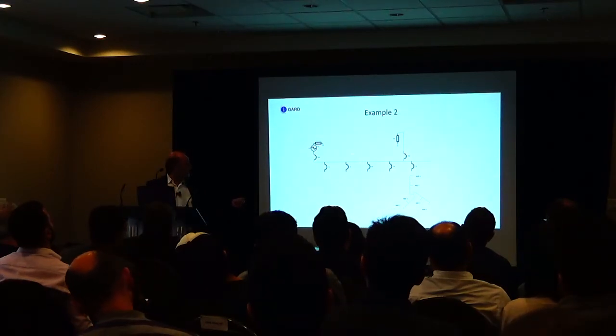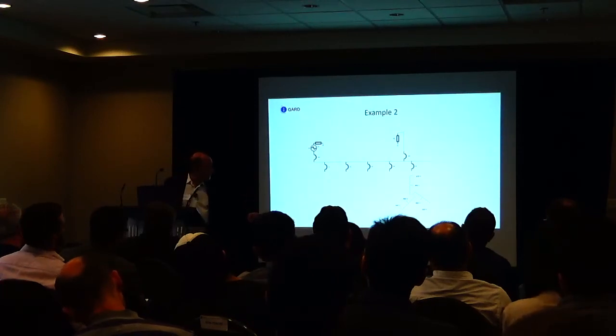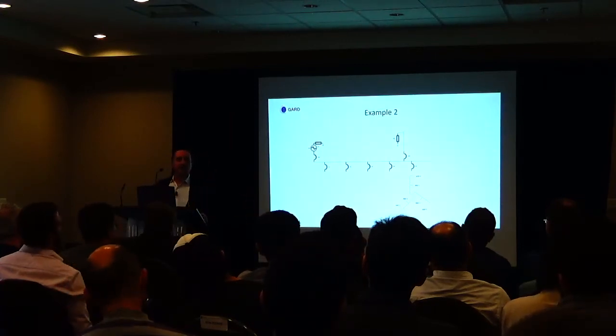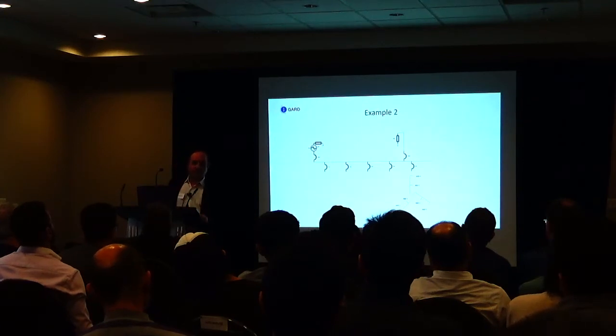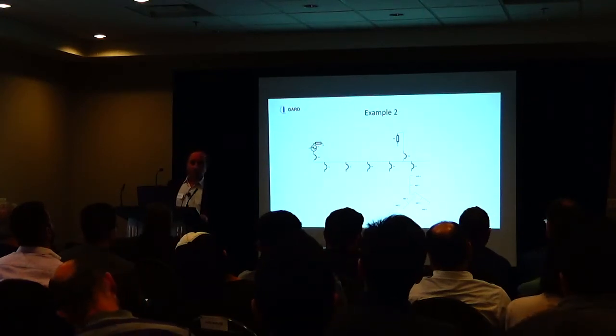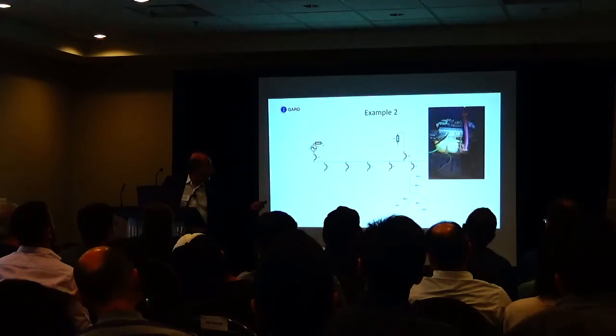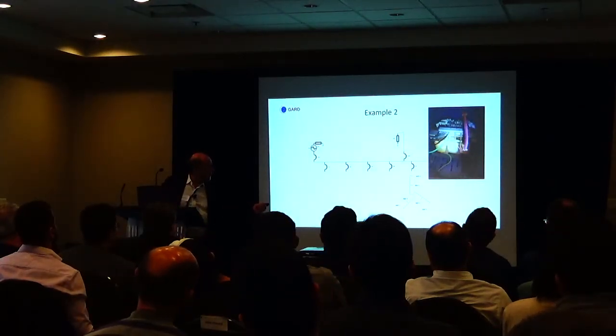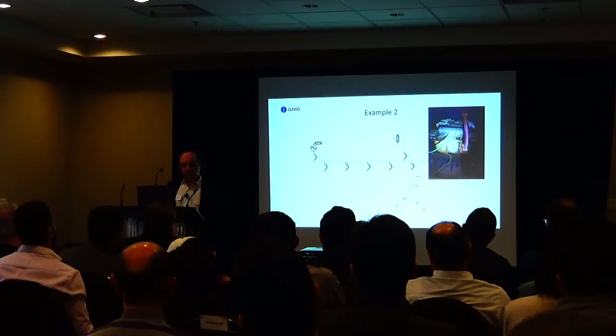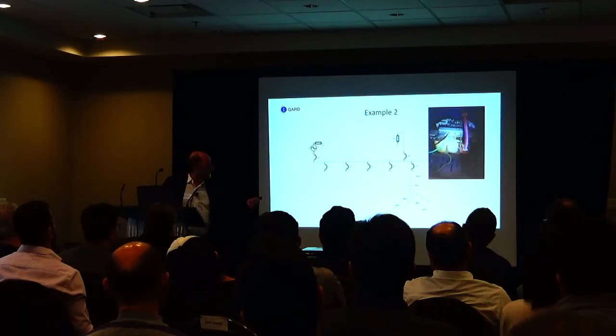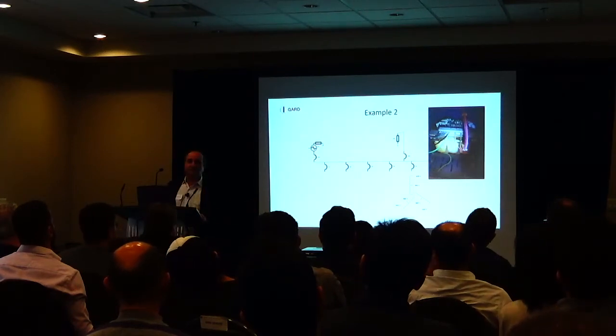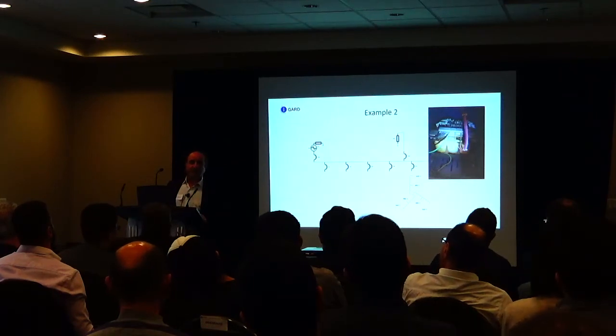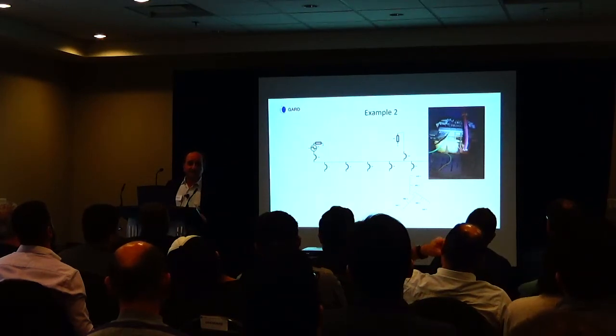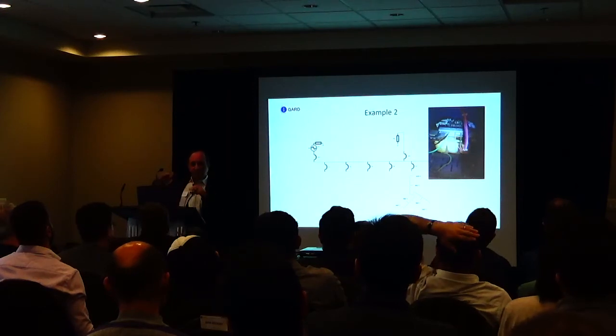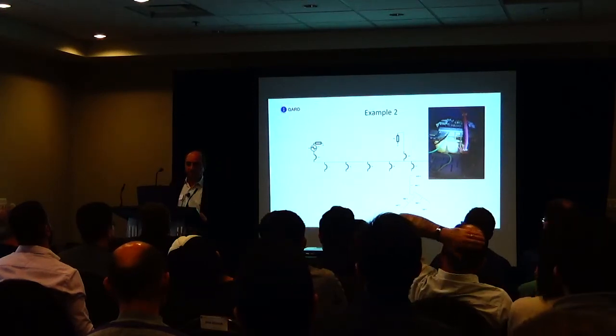I went there to commission this, and what happened was, they found that they had a 480 volt old elevator. So they used an auto transformer for the old elevator. And see that green wire there? That's the XO-HO bushing. That was tying the entire system to ground. So even though we had a resistor up here, that wire made it solidly grounded. And I had 3 of these things. So that prevented the neutral from shifting because we were tying it to ground.